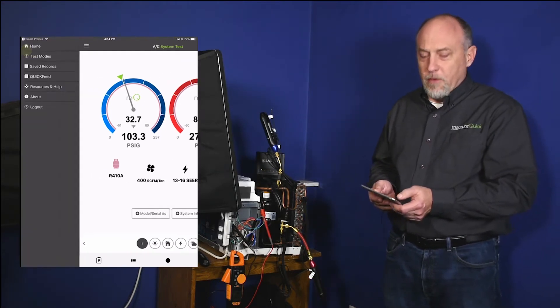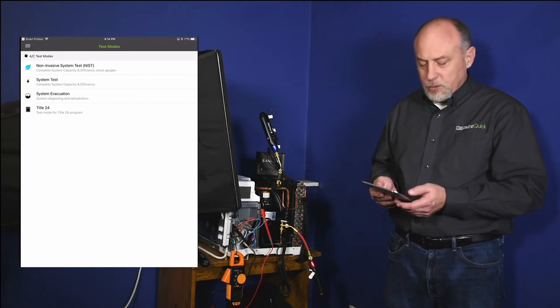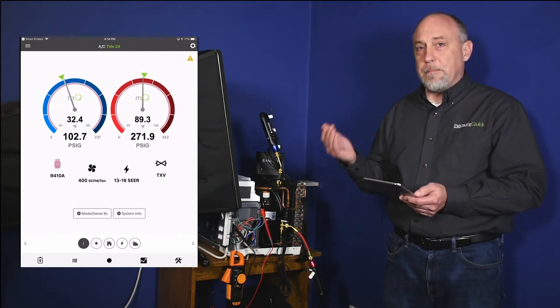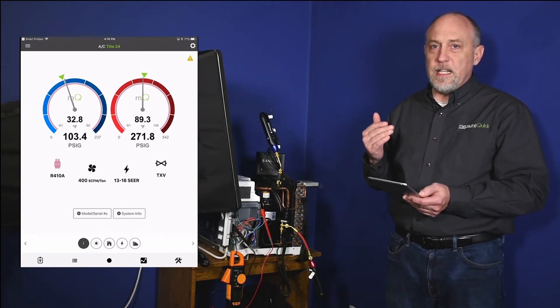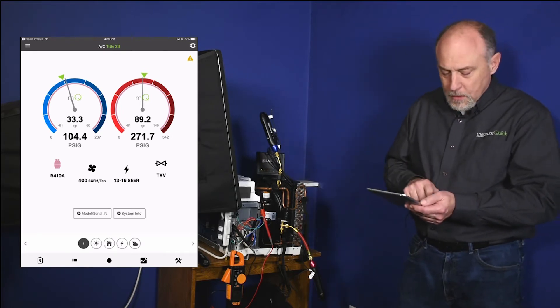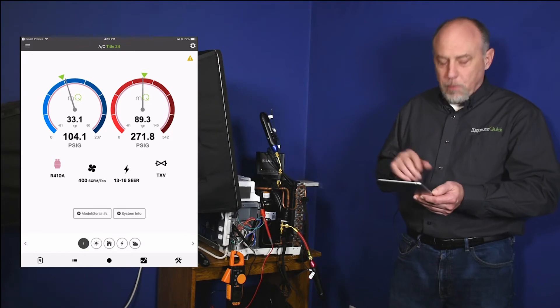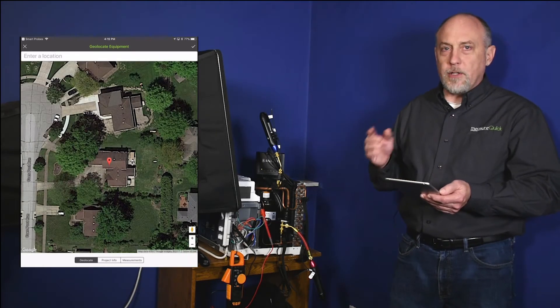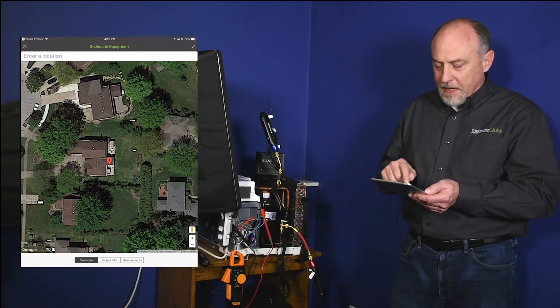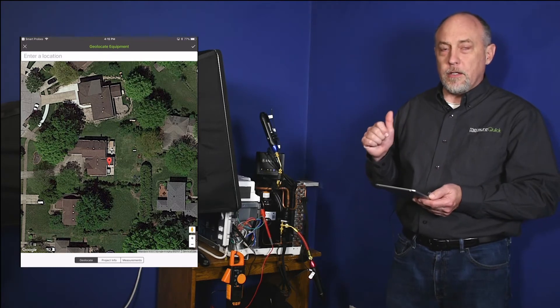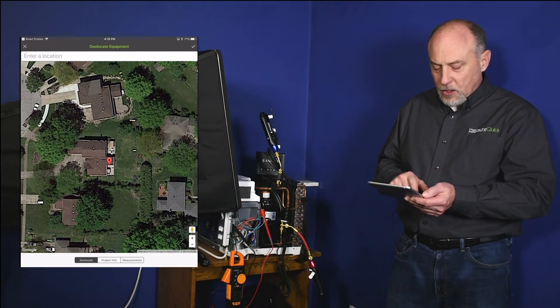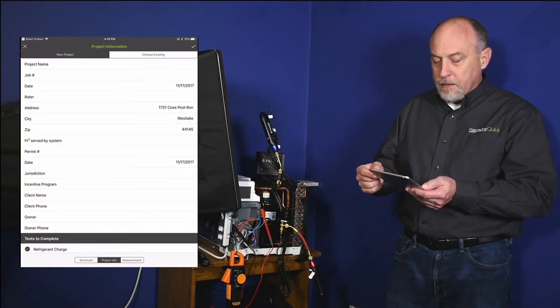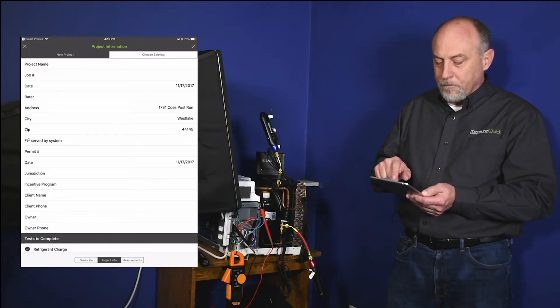So on the side menu we have our menu button here, we've got a test mode. We built a specific test mode in for Title 24. You click on that button and that's going to set up the application for Title 24 testing. It's going to walk you through everything you need to do sort of step-by-step and it's a really easy process. Even I can do it, right? So the first thing you've got to realize is everything we're doing is based upon a geolocation. So I'm going to go ahead and tap on geolocation and we need to mark that equipment. So I'm going to drag this pin over and I'm going to drop it on my condensing unit and that's going to do a couple of different things. Number one, it's going to geocoordinate or locate the condensing unit so we know the exact location. But it's also, when we go into the project information, going to pull in here our address, city and state and zip. All that stuff's done.